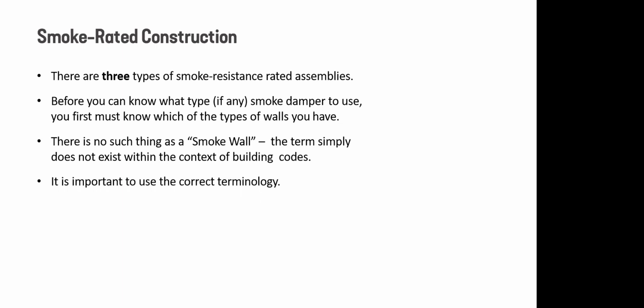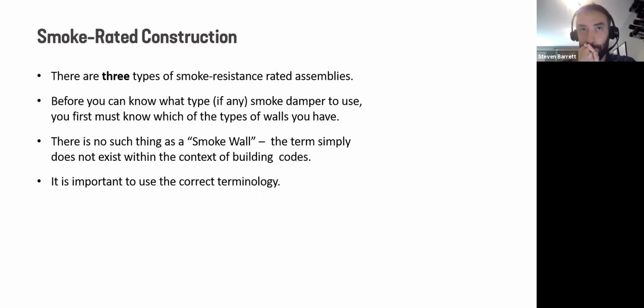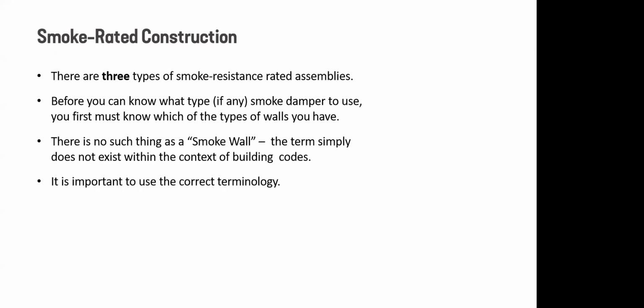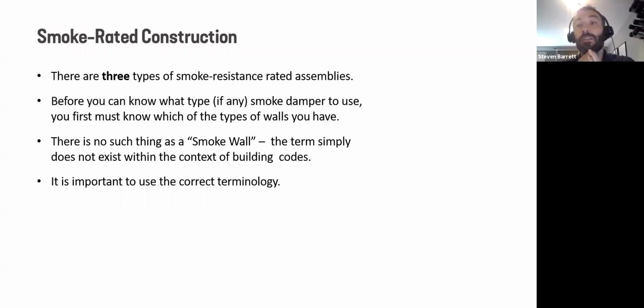There's two actually. I think pretty early on in the presentation, you mentioned temperature ratings. If it's not less than 160 degrees Fahrenheit, then the temperature would be at least 160. You talked about 120 to 160 degrees. So 50 above ambient is the minimum temperature that the fire damper must activate at, not to exceed 160. So in a typical room that's 70 degrees, let's say, plus 50 is 120, the minimum damper activation temperature. But if for some reason the room was pretty hot, then 50 plus ambient could exceed 160. So 160 is the max.